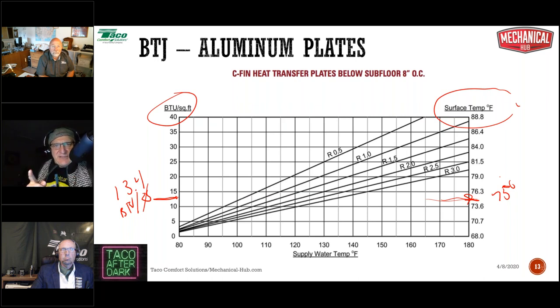Now, what do I have to do to get there? Now I've got to figure out the finished floor R value. What's the material and what's its corresponding R value? Radiant manufacturers have books you can look this stuff up in, which is very helpful. But for our purposes, let's presume it's a good residential carpet and pad with a combined R value of 2.0. To find the water temperature, we follow our BTU per square foot line over, going from left to right, until it meets the R value 2.0 line. Where the two lines meet, we drop straight down to find our supply water temperature. In this case, it's about 122 degrees.